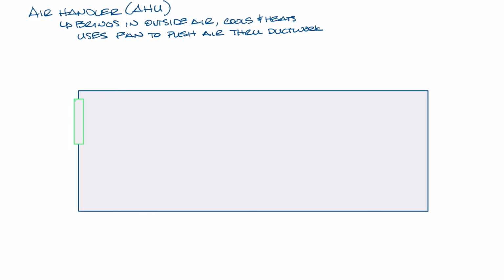The outside air dampers control how much outside air enters the air handler. How much air you bring in depends on the building's load, as well as how much outside air you want or need to have in your application. In general, you need to bring in some amount based on the area of the building and the number of occupants. Or you could have 100% outside air depending on the application and the system. The outside air damper could be set for a certain amount or percent of outside air as well, or it could modulate the volume based on conditions in the building.